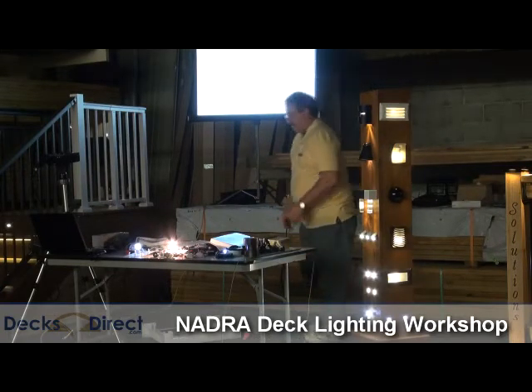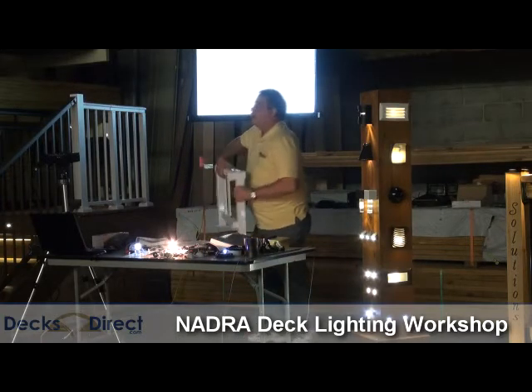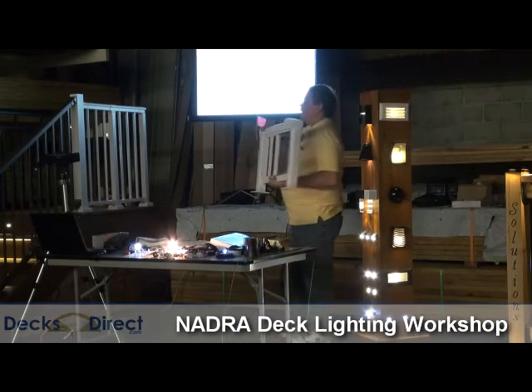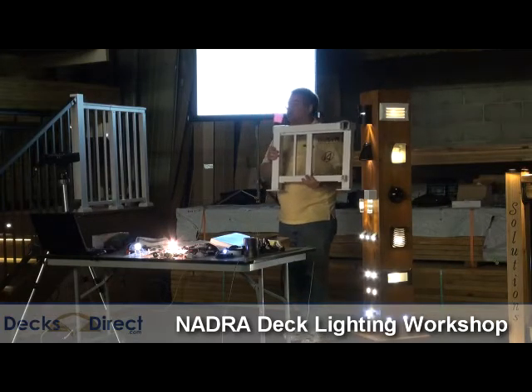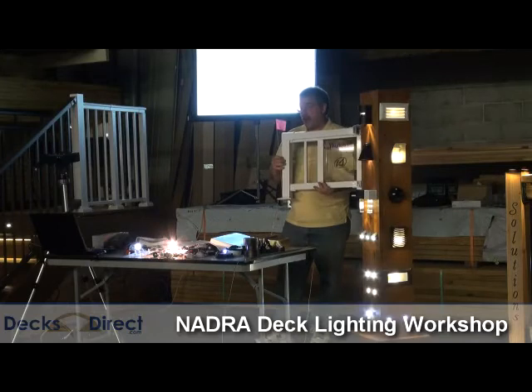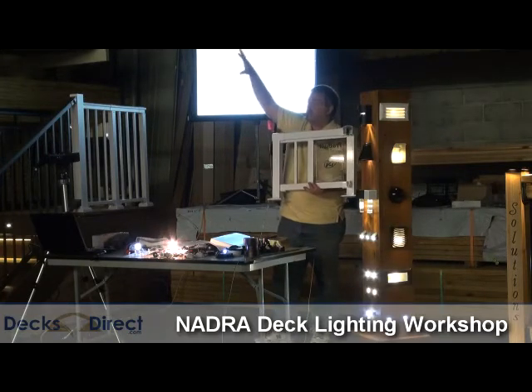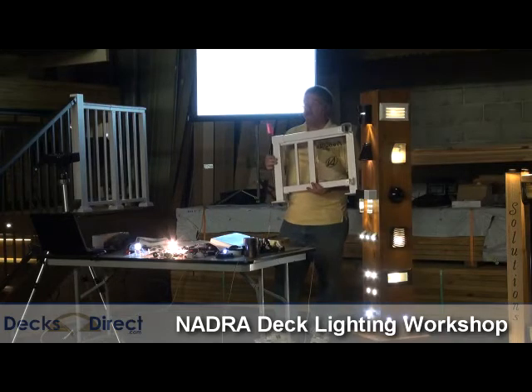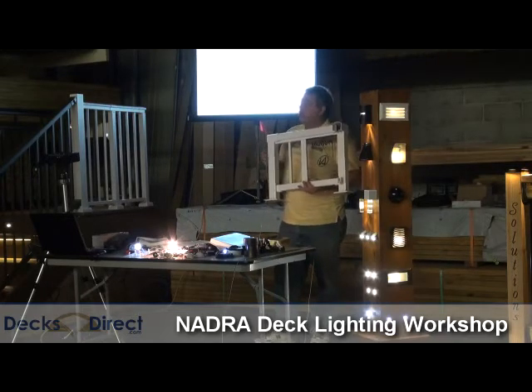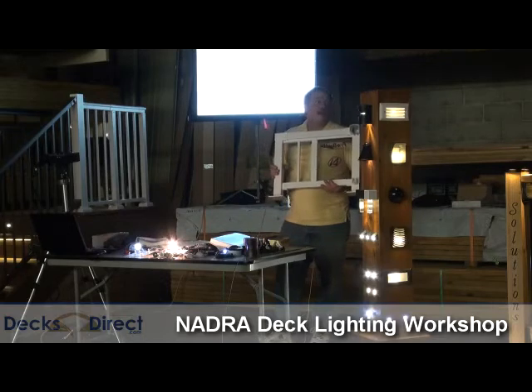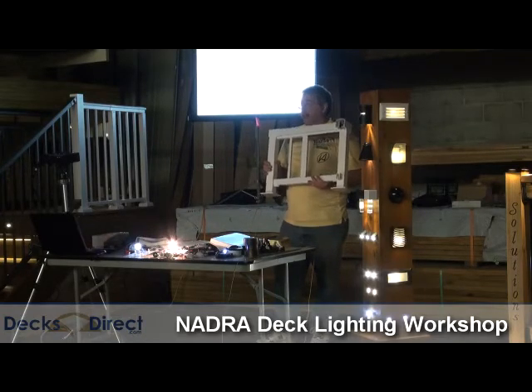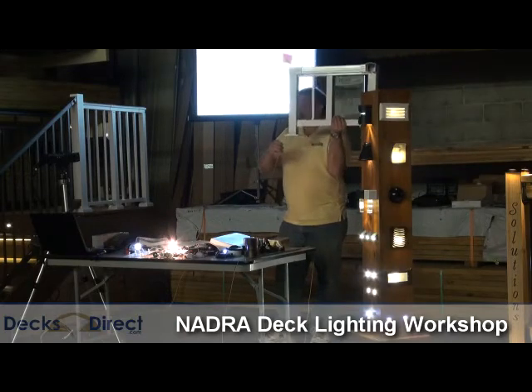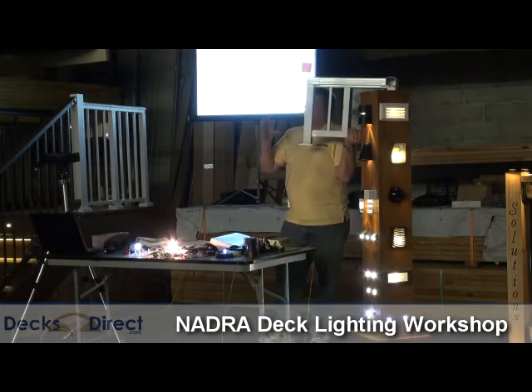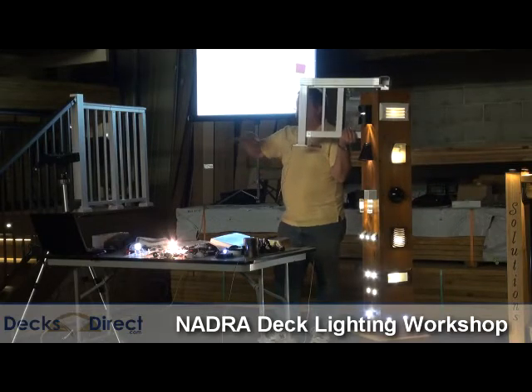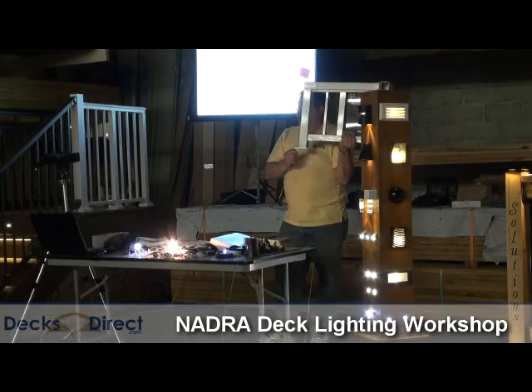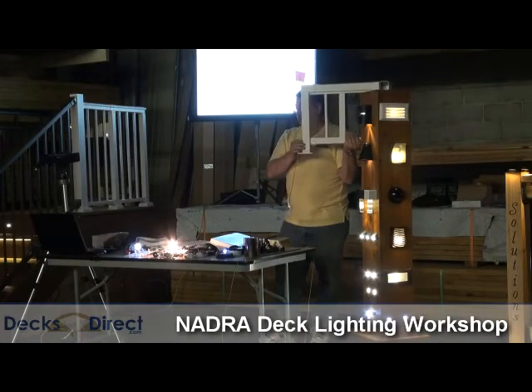The other thing we talked about on decks are these aluminum rails. If you've got a hot tub, all the metal parts within 60 inches of the hot tub have to be grounded on the same ground plane as the hot tub. When birds sit on phone or power lines, they don't get electrocuted because they're on the same level of electricity, the same, what we call, I can't pronounce it very well, equipotential bonding or neutralization. We need to ground our rails when they're near that hot tub. For the same reason birds don't get electrocuted, if you're in the hot tub and you get a voltage charge across it and you touch the rail, you won't get electrocuted. So every piece of metal within 5 feet has to be done.